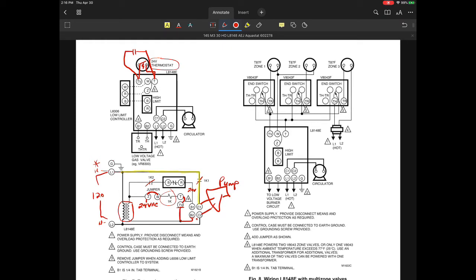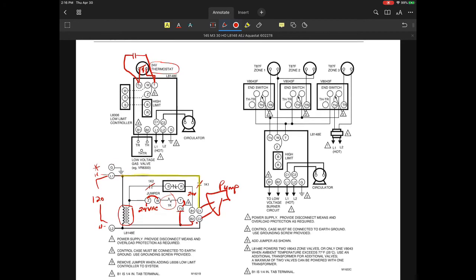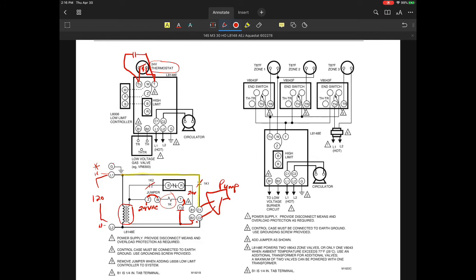How does this look with a zone valve system? Well, you could certainly have used a zone valve system with the other type of application, with the A model, but your wiring would have been slightly different. In this example, you would have had to have some sort of transformer that would allow you to power up 24-volt devices, assuming you're using a 24-volt actuator. So the Aquastat now, what we have to find out is how they're going to utilize this on these zone valves. This Aquastat is going to look for a heating demand, not from a thermostat, but what will happen is the thermostat will actually power up the zone valve actuator.